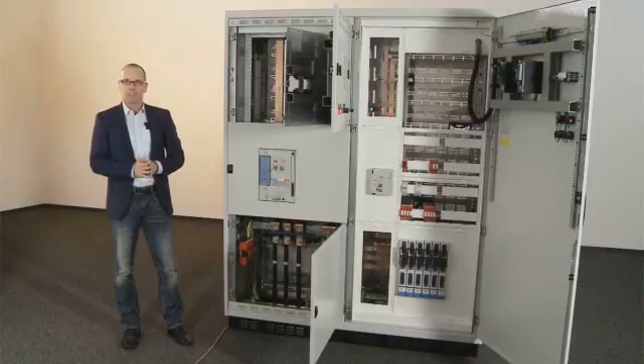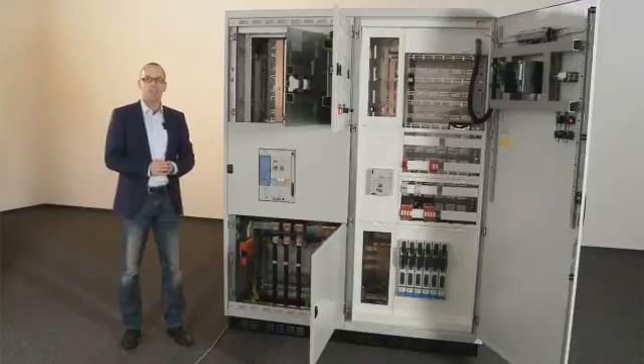Dehn Short has a typical response time of just two to three milliseconds. The impact energy is thus considerably reduced, significantly limiting the fatal effects of an arc fault on the installation and persons in the vicinity.